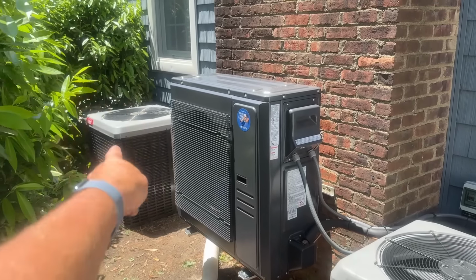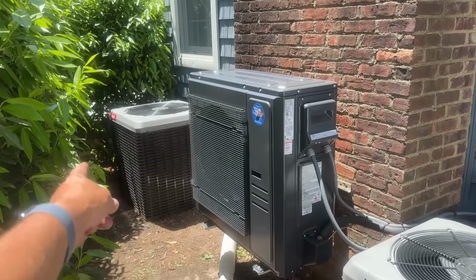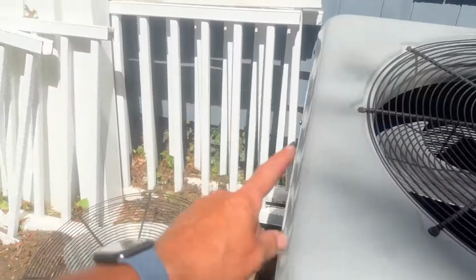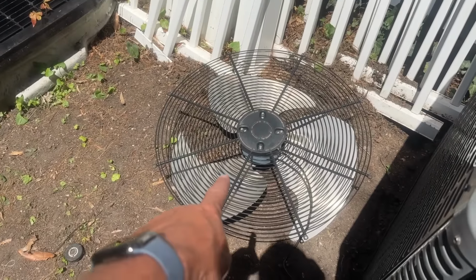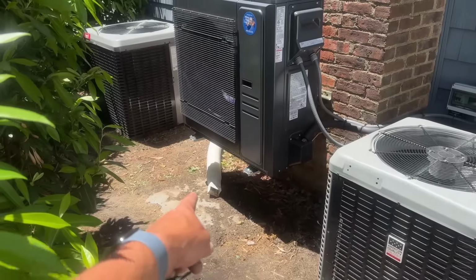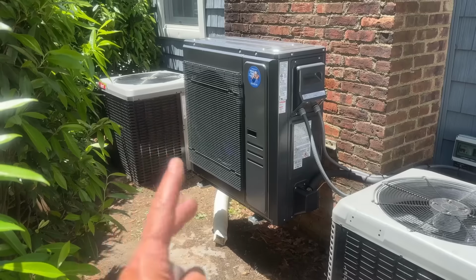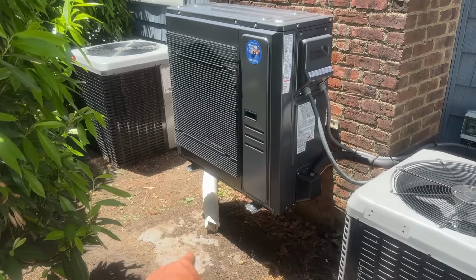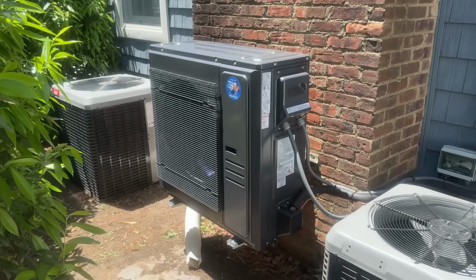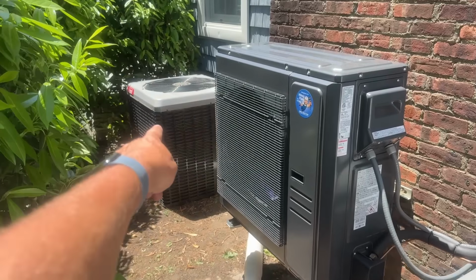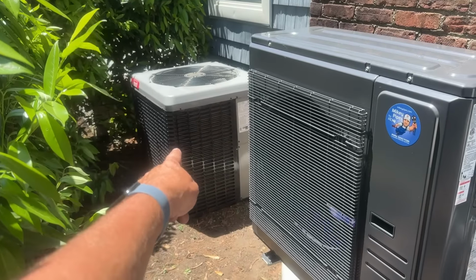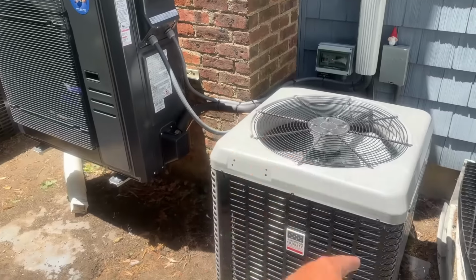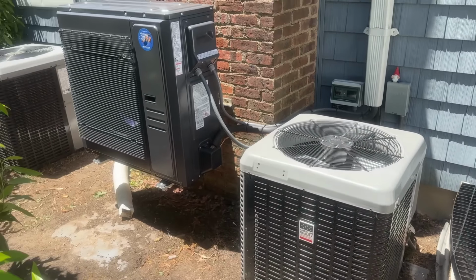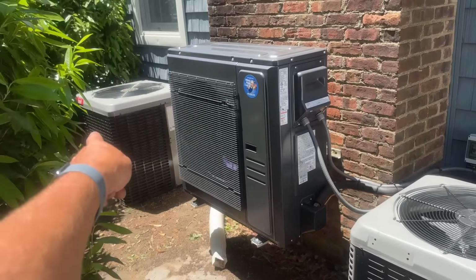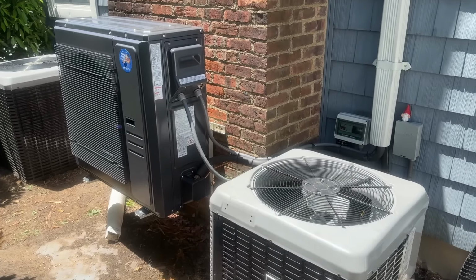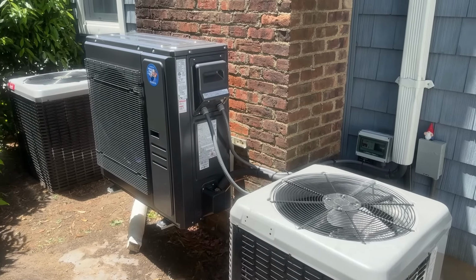Unfortunately, we ran into a problem with the Coleman while doing preventative maintenance on the 3 other systems here. We left them the condenser fan motor from the old 3-ton unit that was here. What's odd here is that 3-ton outdoor unit was paired with a 5-ton indoor, right? That 3-ton is paired with a 5-ton indoor. And I have no idea what's going on with the other 2, but we were asked just to do maintenance. We did that. That one's not cooling. The other 2 are. And we are good to go, folks.